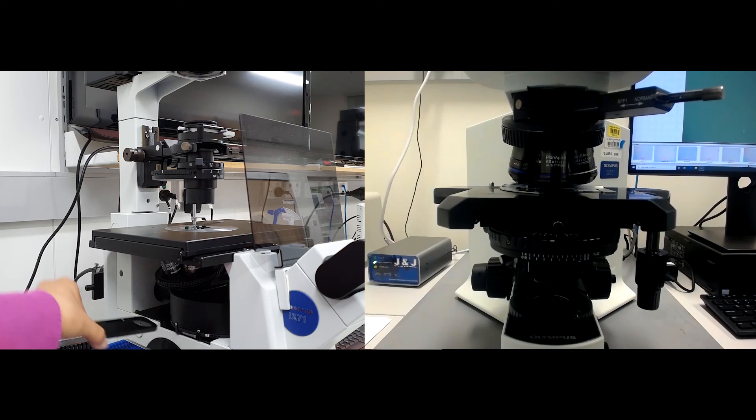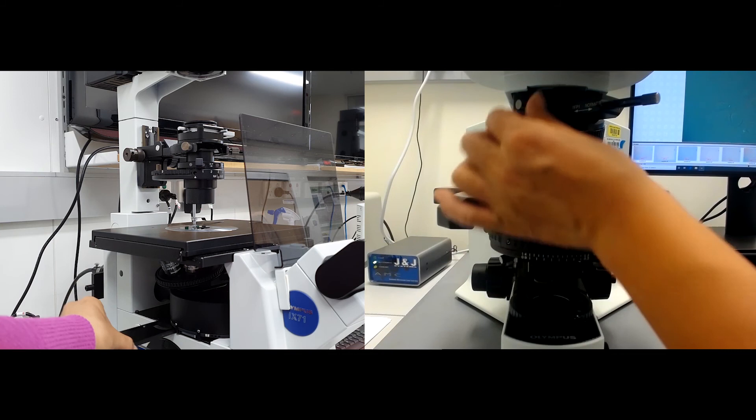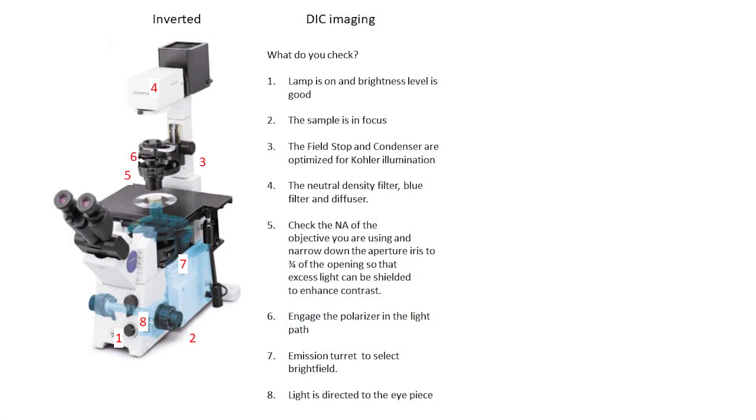If you are not doing DIC but you are doing fluorescence imaging and you want to deconvolve the images later, be aware that the DIC components can affect your point spread function and image quality or your deconvolution image.